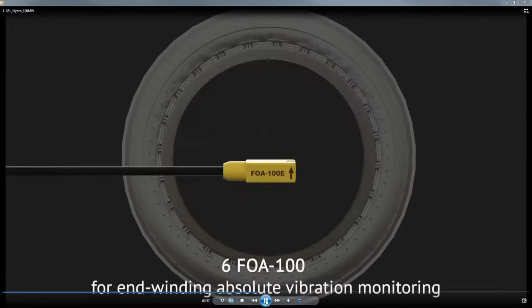Okay, an example here installed. And then we recommend 6 fiber optic accelerometers for absolute vibration monitoring of the end windings. In many cases, when I mention this, people say, well, isn't that basically a turbo generator issue? And although it is quite frequently or more frequently a problem with turbo generators because of the length of the end windings and there's less support. I mean, they can go out 2 meters and there's not much support, so the vibration, the energy, gravity, and all that can cause issues.